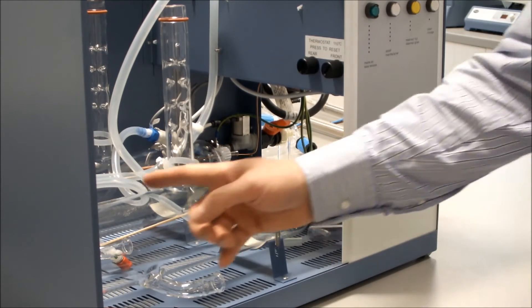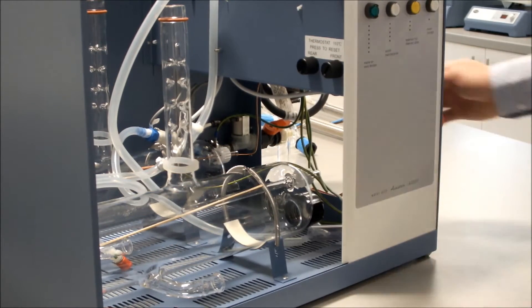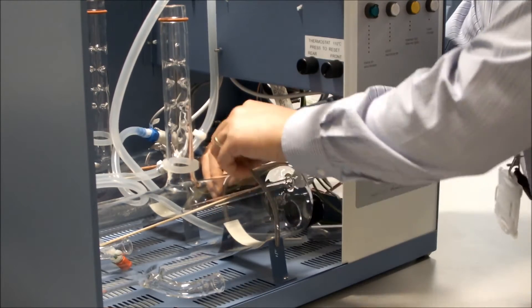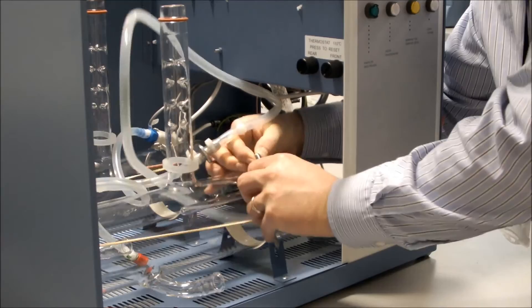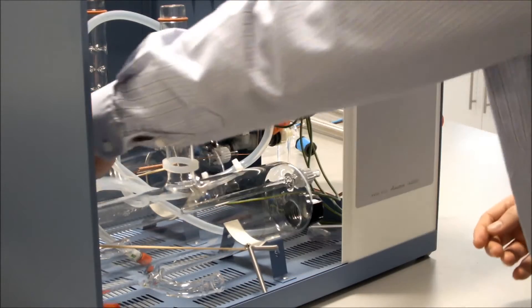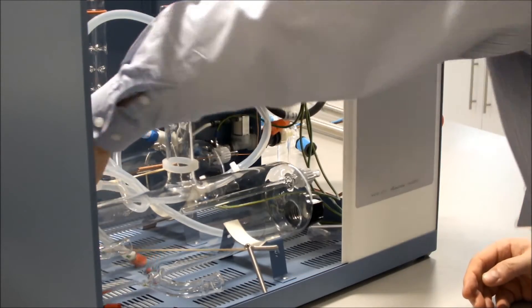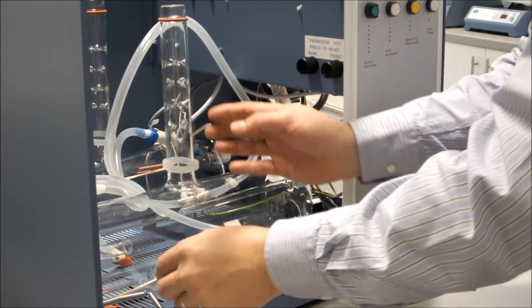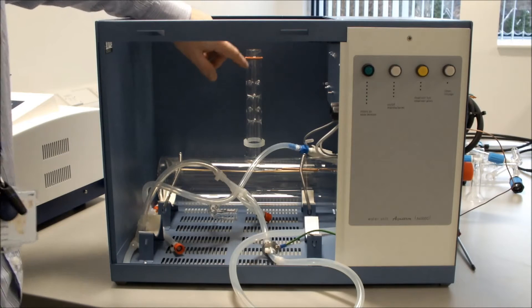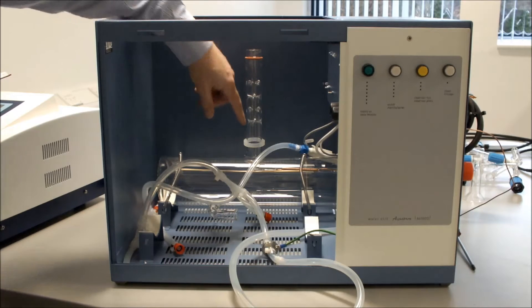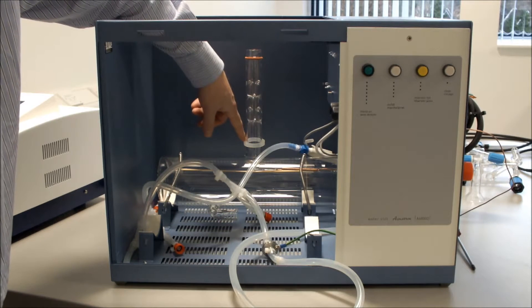The first thing we do is remove the retaining springs. The boiler can be lifted straight out. The next thing to do is to check the O-ring seal and the stabilizing seal on the rear boiler itself.